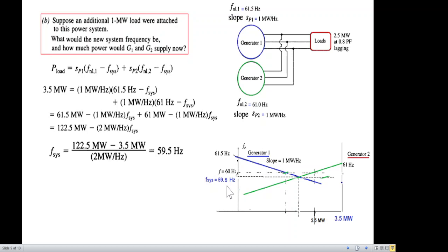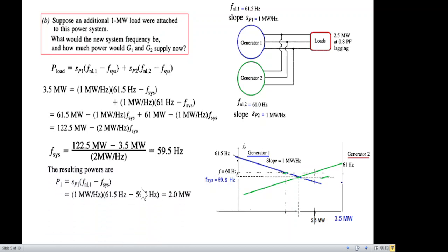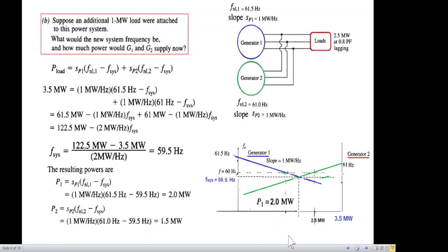The frequency has dropped to 59.5 Hz. In many cases, a drop of 0.5 Hz may not be acceptable. Calculating load sharing at this new frequency: generator one is sharing 2.0 MW and generator two is sharing 1.5 MW, totaling 3.5 MW. Generator one is sharing more power than generator two.